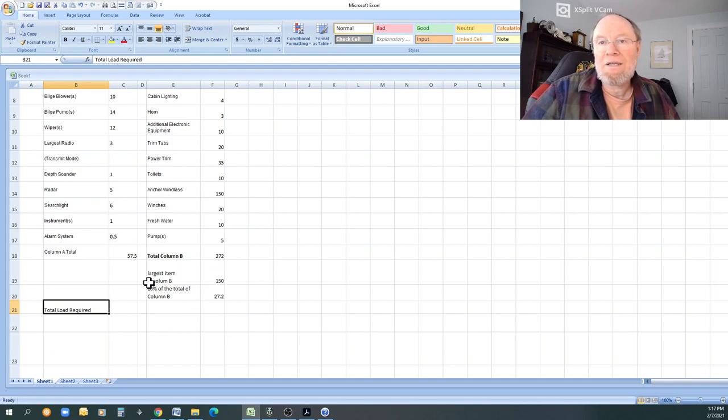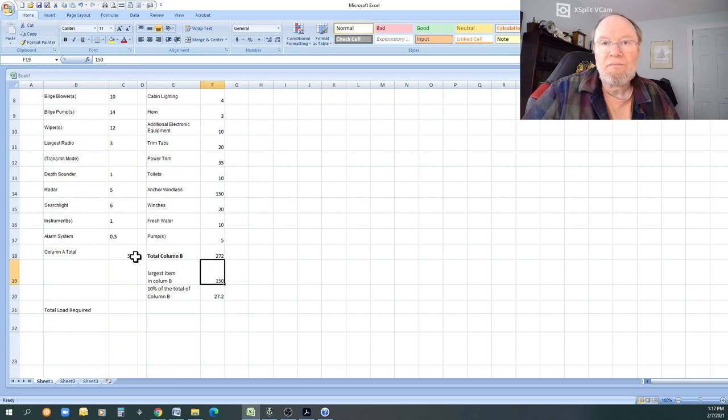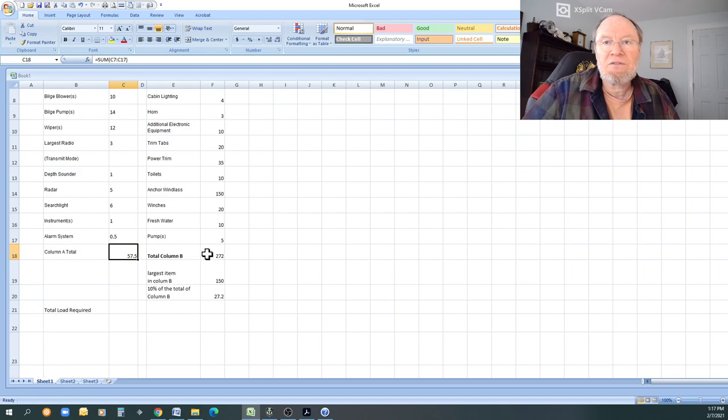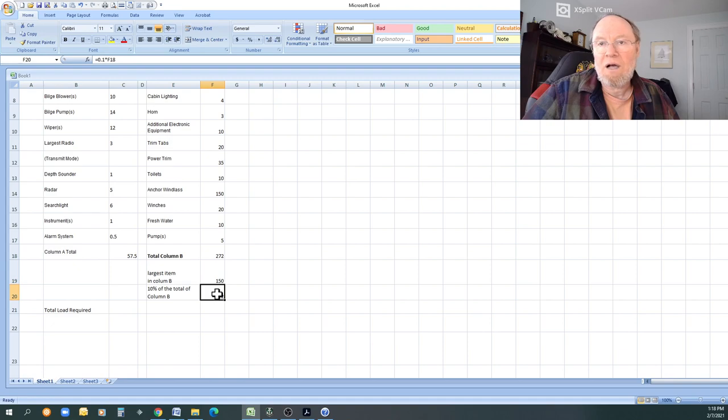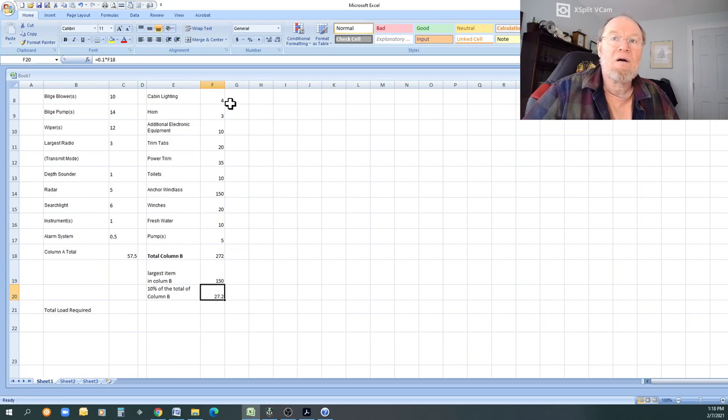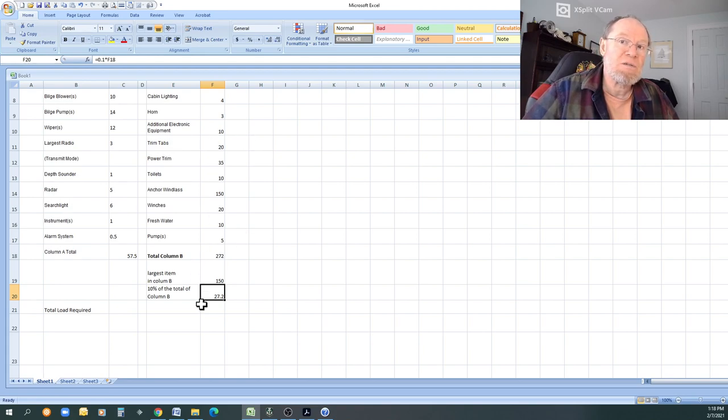So now what we're going to do is we need to total this up. Which one is greater of these two? 10 percent of the largest item, obviously the largest item, right? Total column A, column B, largest item that will be greater than the total of column B. Now, if you've got a whole bunch of other things in column B and it gets up to 300 amps or something like that.